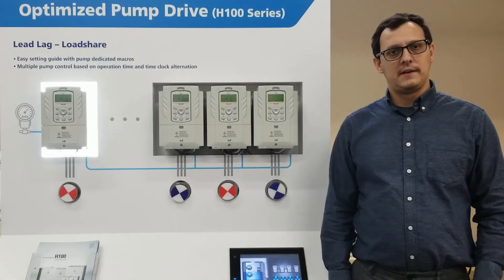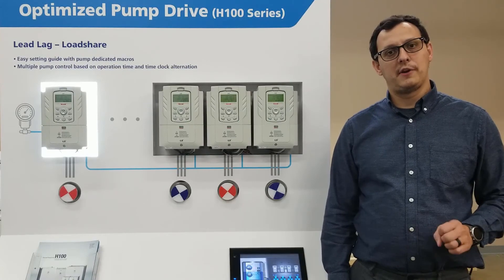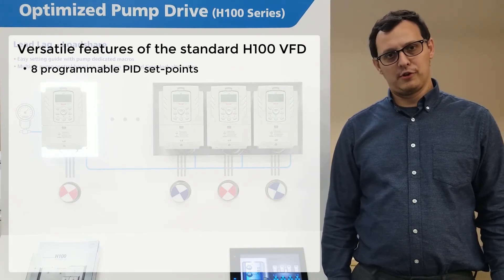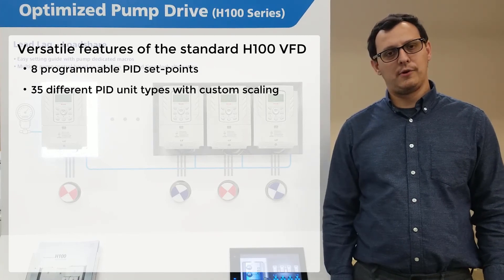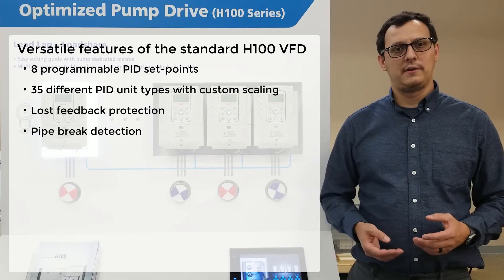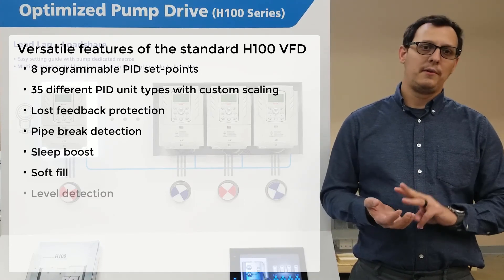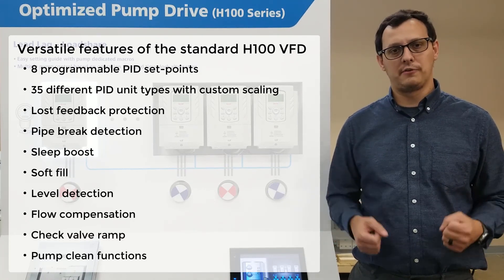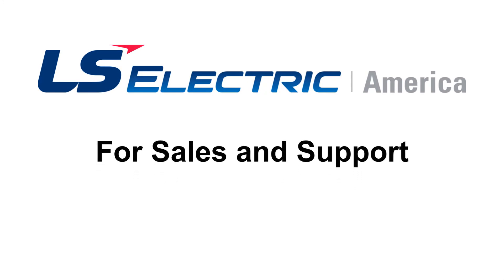In addition to the lead-lag function built into the H100, the H100 has many nice standard PID functions and pumping features to help you. Eight programmable PID set points are available, and 35 different PID unit types with custom scaling. Additional features include lost feedback protection, pipe break detection, sleep boost, soft fill, level detection, flow compensation, check valve ramp times, and pump clean functions. Thank you for watching — please feel free to contact us if you have any questions.